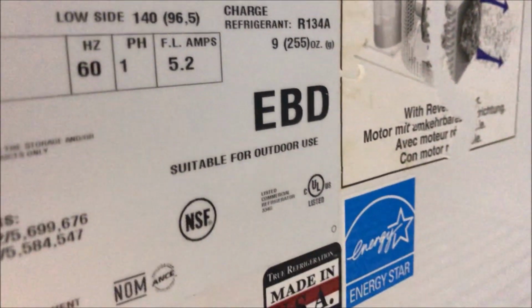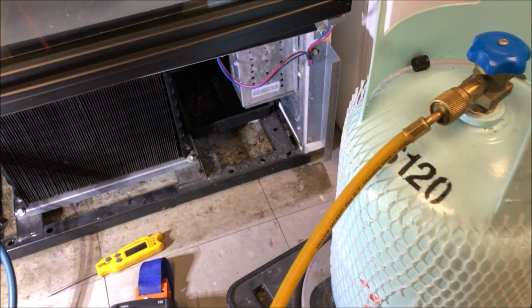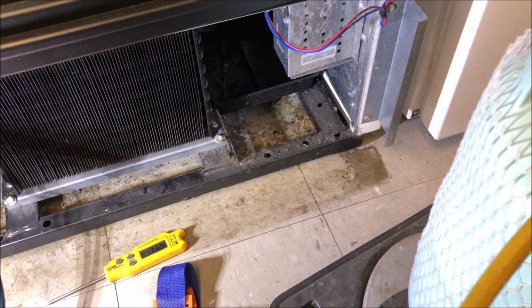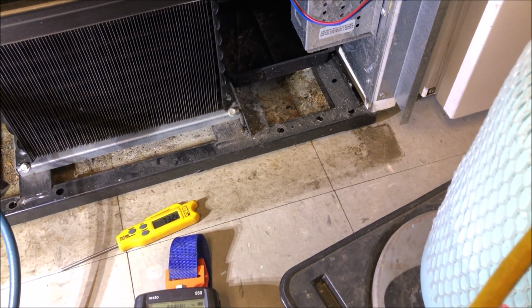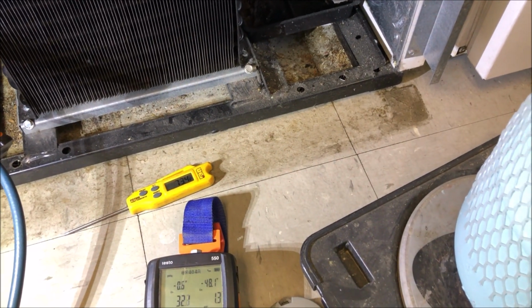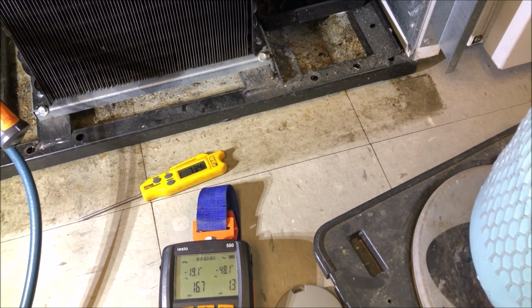So based on the pressures we have, we're either restricted or we have a low charge. So I just checked the charge there, it's 9 ounces. Okay, so the reason that I checked that, I wanna see how big this leak is if we do in fact have a leak. So at this point, a lot of people will just go right into the leak test, but what if there's not a leak? Like you're wasting an hour or whatever trying to find a leak. So I wanna rule out there's no restriction.